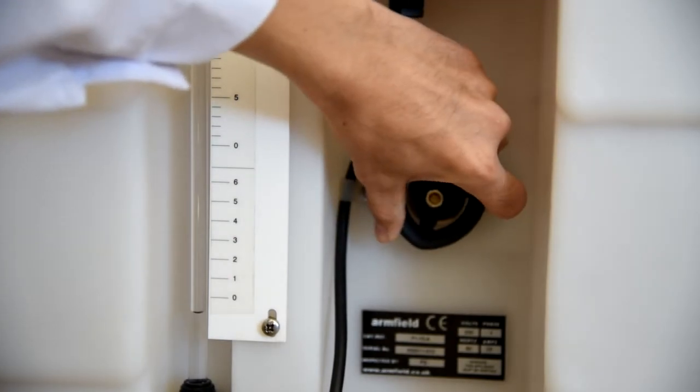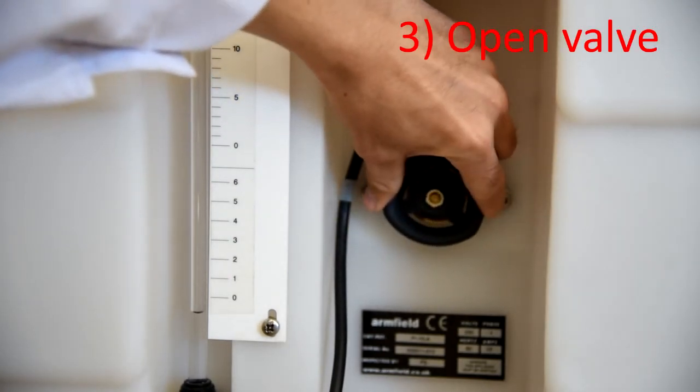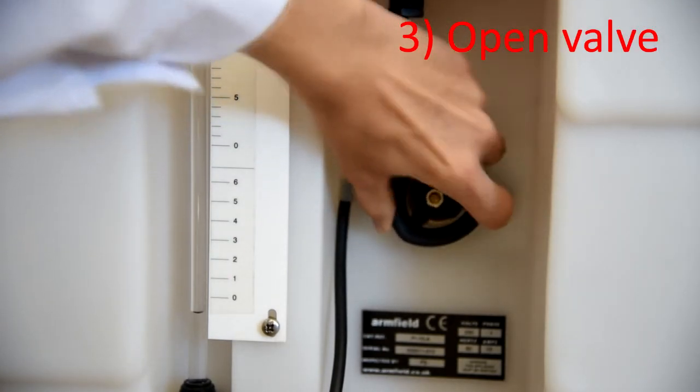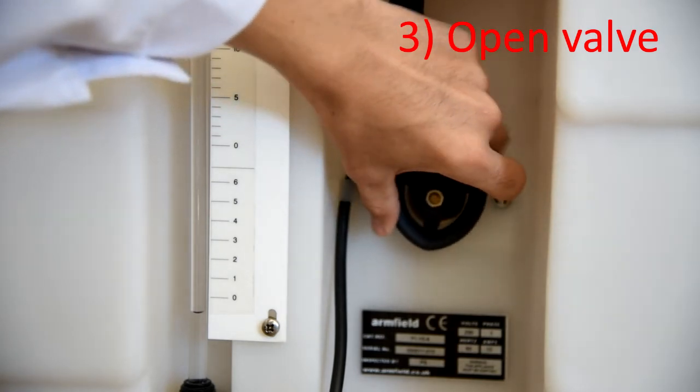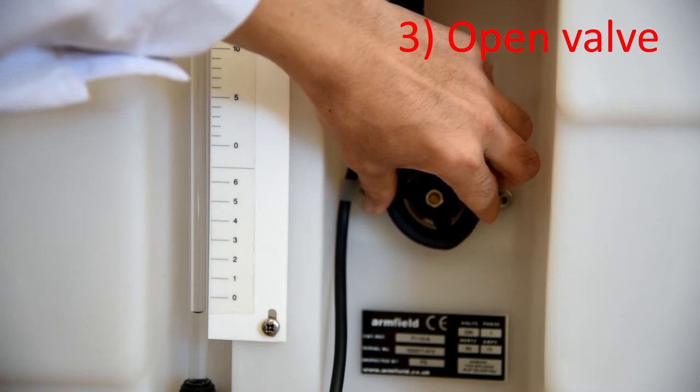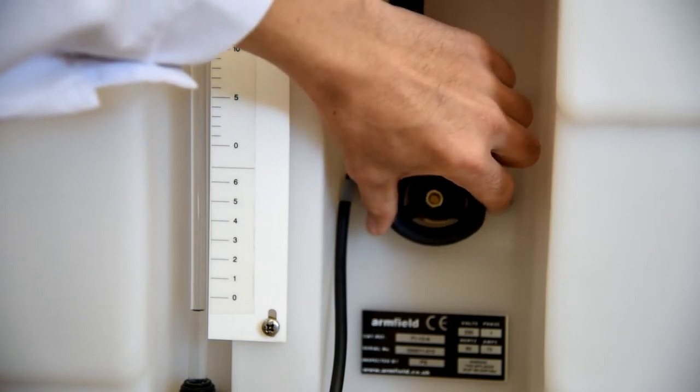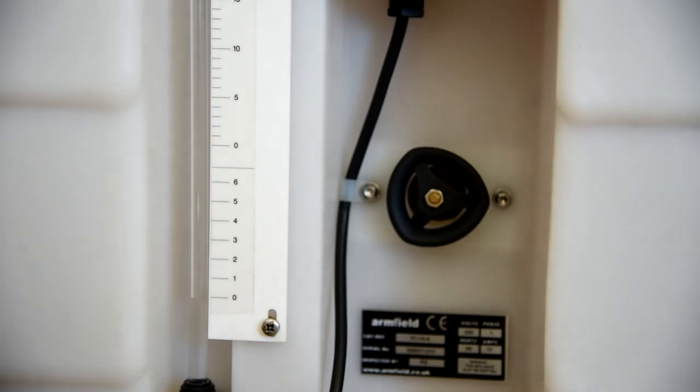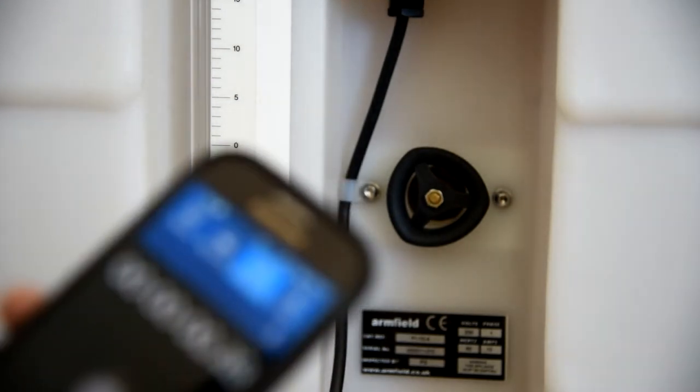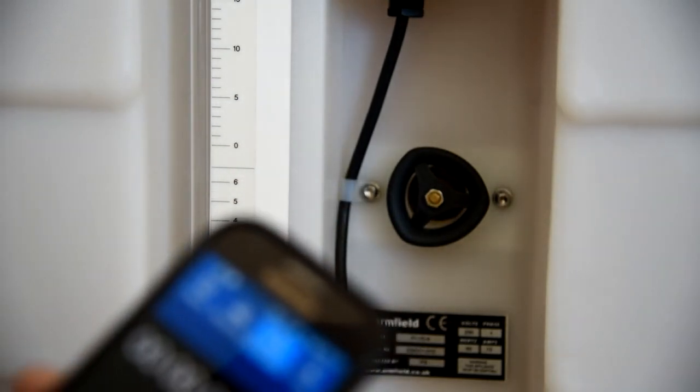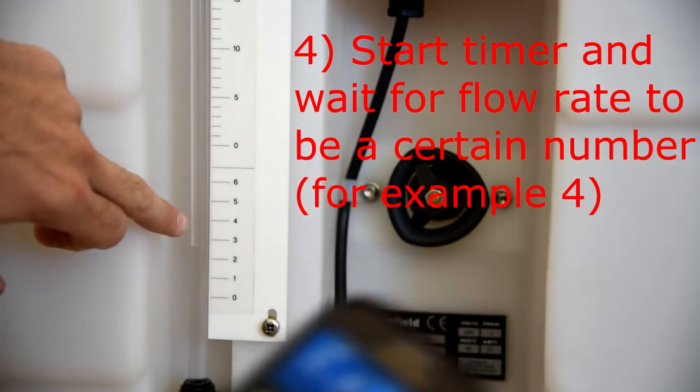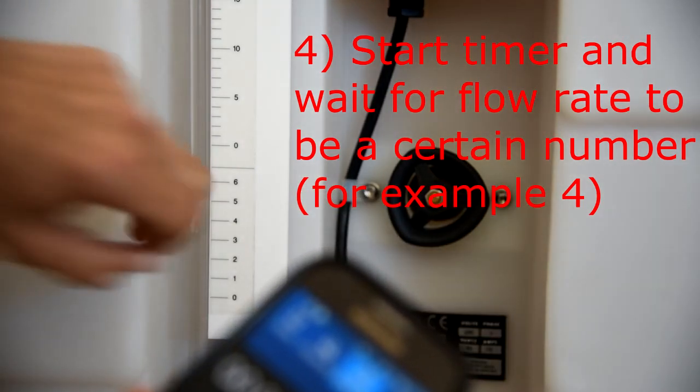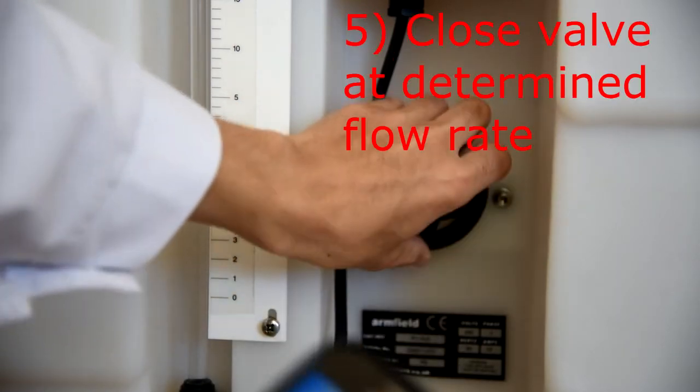Here, we should open the control valve in anti-clockwise direction. And wait, and start timing. And we should wait till it will be, for example, 3 liters, and stop.